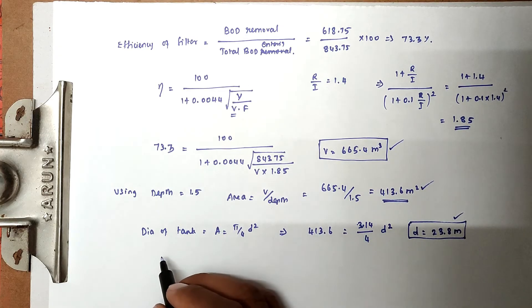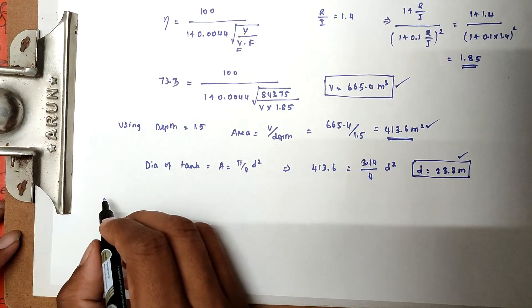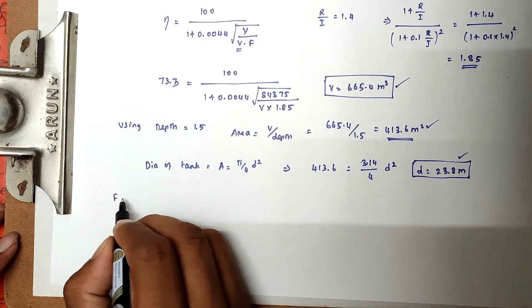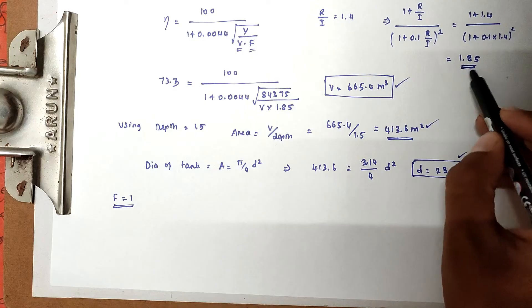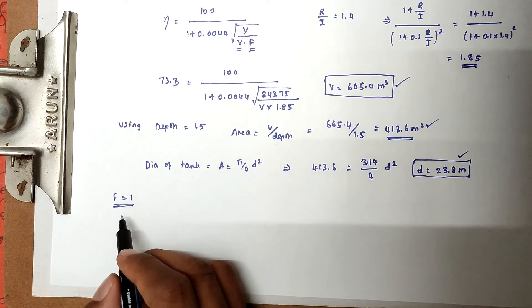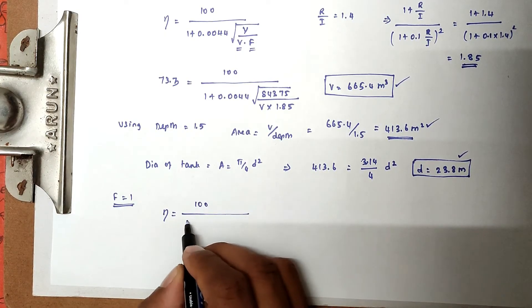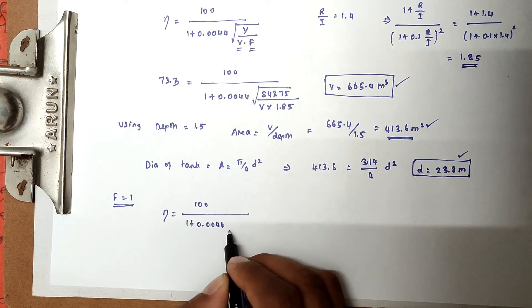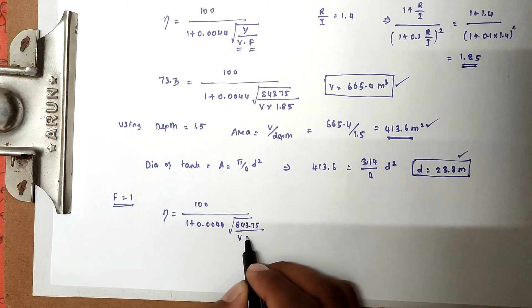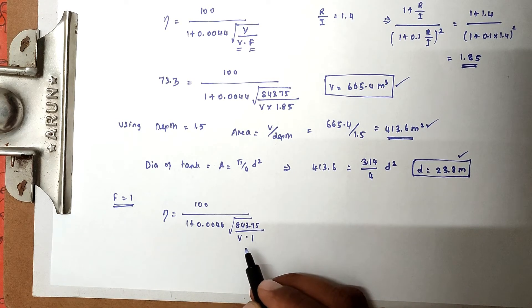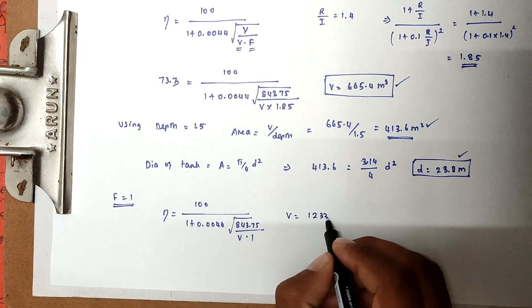Now for the standard rate trickling filter, the recirculation factor F equals 1. Substituting into the NRC formula: 73.3 = 100 / (1 + 0.0044 × √(843.75 / (V × 1))). Solving this gives volume V = 1,233 m³.